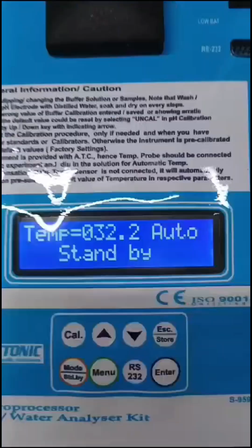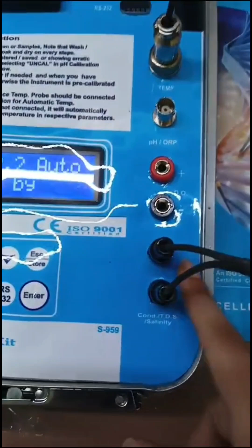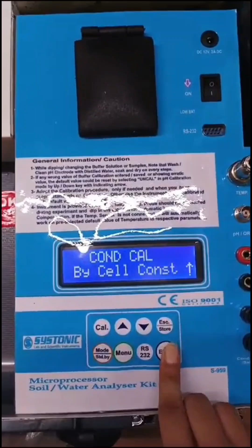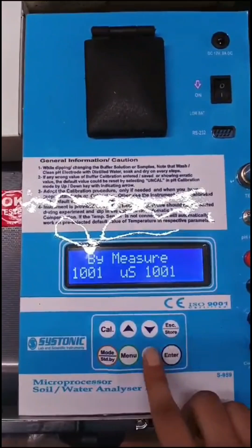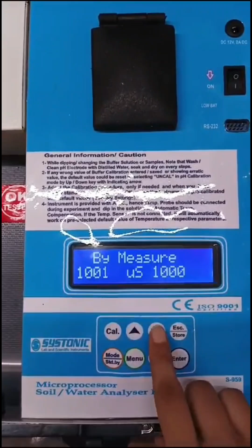First you have to escape. For that you have to first connect the conductivity cell and dip this cell in 1 millisiemens standard solution. To prepare this solution, the instructions are given in the manual. Now again go to cal and to conductivity, then press enter. After that you have to go to by measure and then press enter.